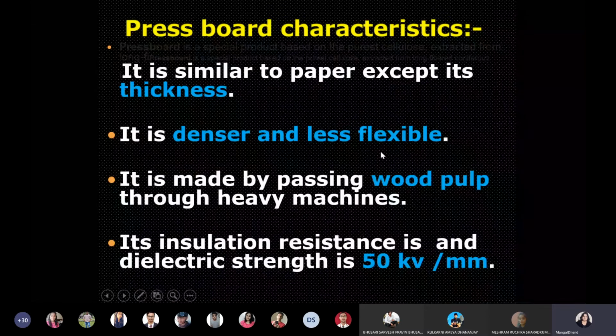So it's less flexible. It is made by passing wood pulp through heavy machines. So wood pulp is used to make the pressboard. Its insulation resistance and dielectric strength is about 50 kilovolt per mm. Okay, so dielectric strength you must remember. Already I told you, dielectric strength means at what voltage it will break down divided by the thickness. So if you consider 1 mm thickness of pressboard, its breakdown voltage will be 50 kilovolt.